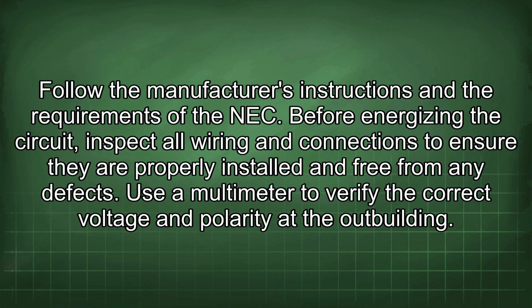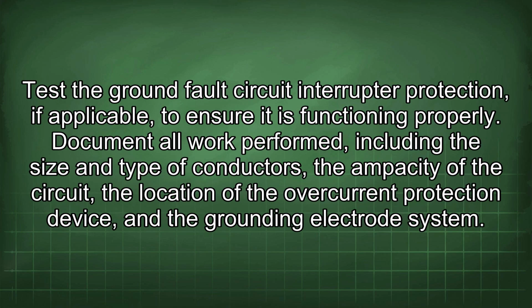Before energizing the circuit, inspect all wiring and connections to ensure they are properly installed and free from any defect. Use a multimeter to verify the correct voltage and polarity at the outbuilding. Test the ground fault circuit interrupter protection, if applicable, to ensure it is functioning properly.